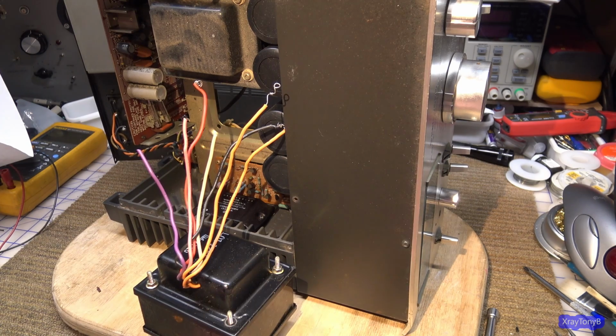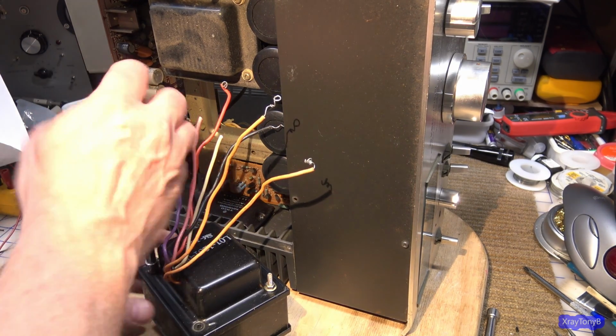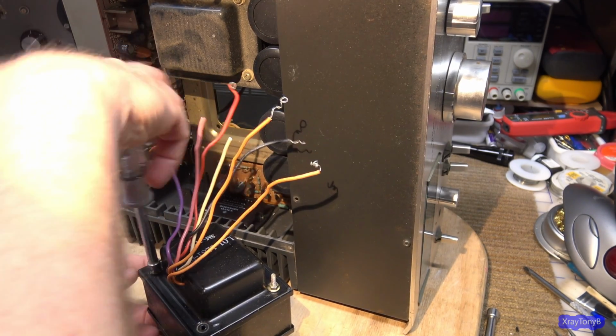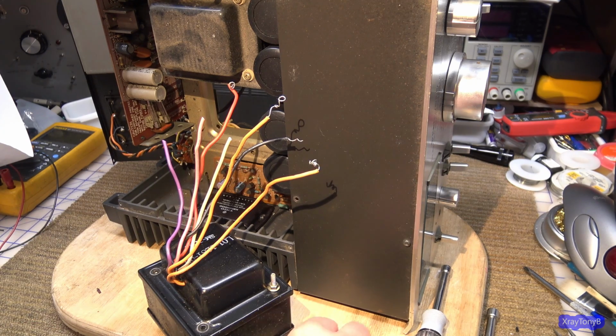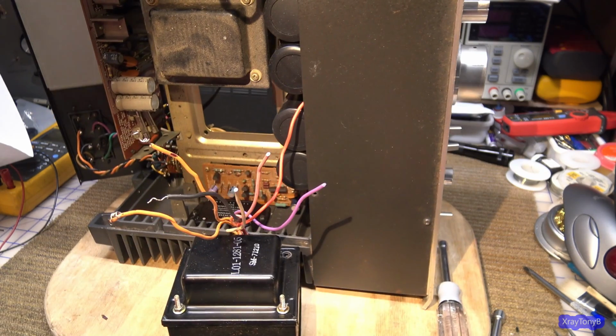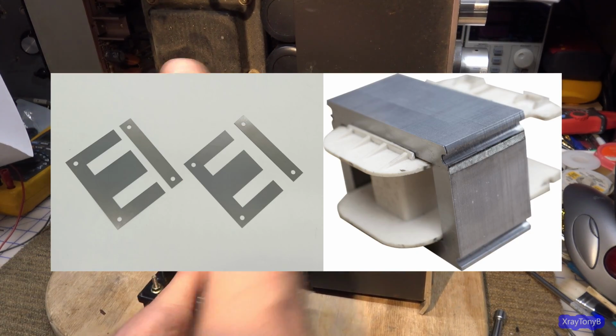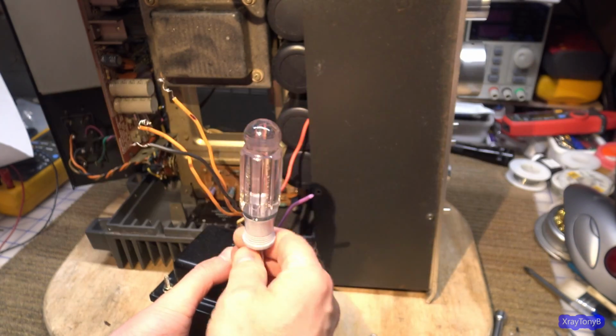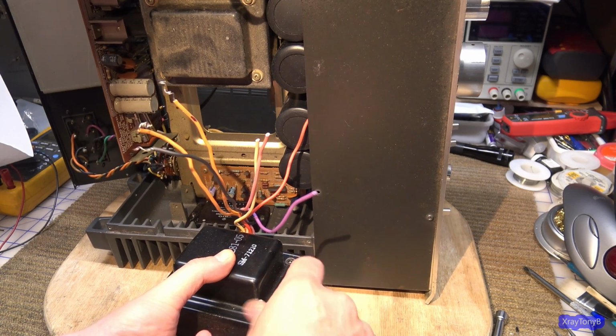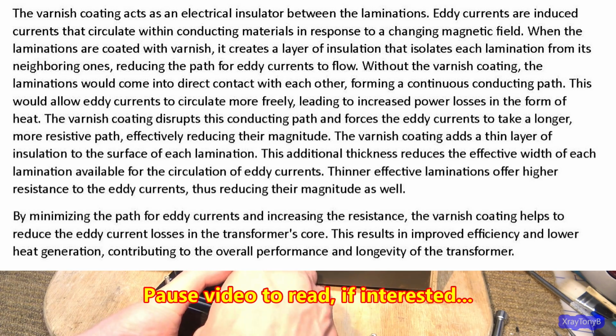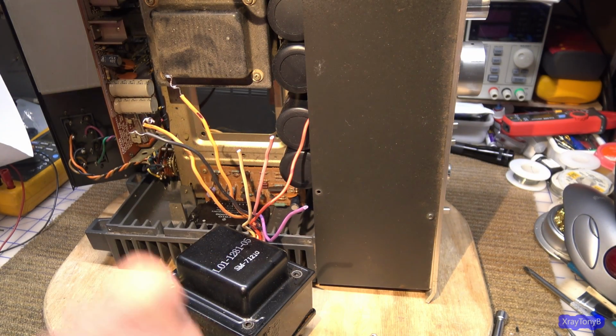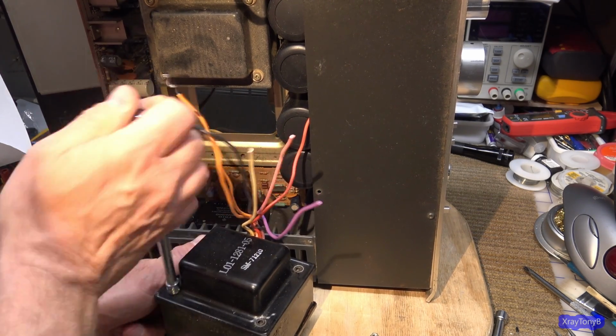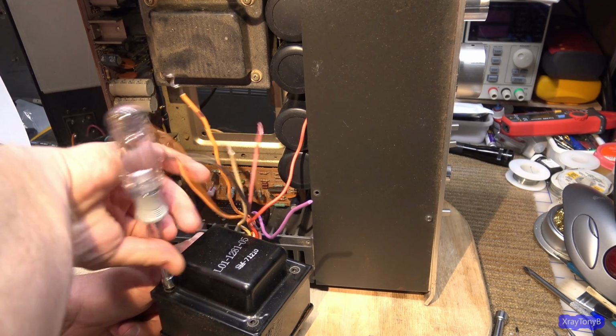Now the other thing you have to watch with old transformers is if the enamel or the varnish on the laminations has broken down, causing the laminations to short out. And what do I mean by that? Well, the core of the transformer is not a single piece of steel or iron. It's actually many thin sheets laminated together, and that helps reduce the effect of the eddy currents in the core of the transformer. If you had one giant chunk of metal there for the core, the eddy currents would cause it to be very, very inefficient. The transformer would consume a whole lot of energy and convert it into heat pretty much through the eddy currents.